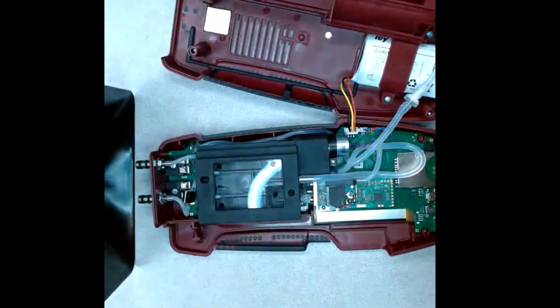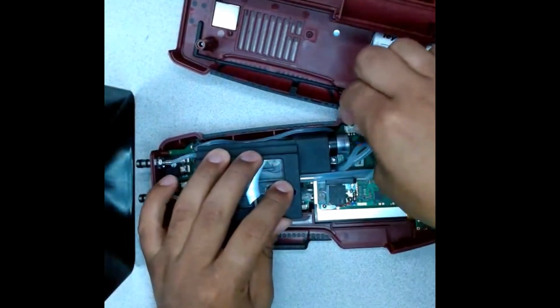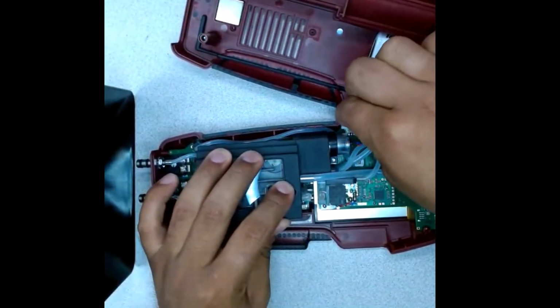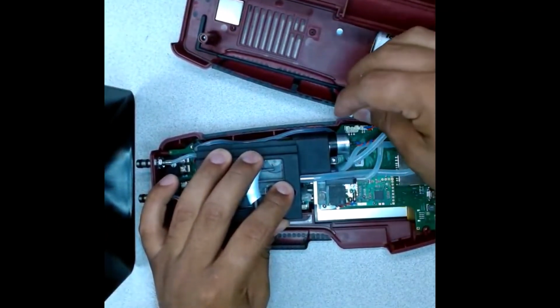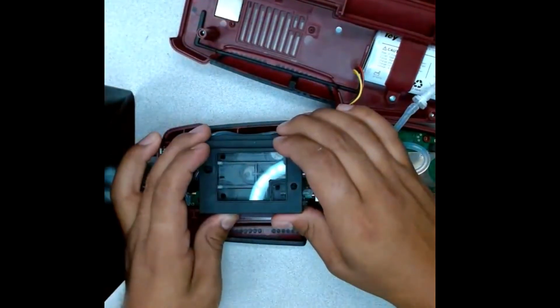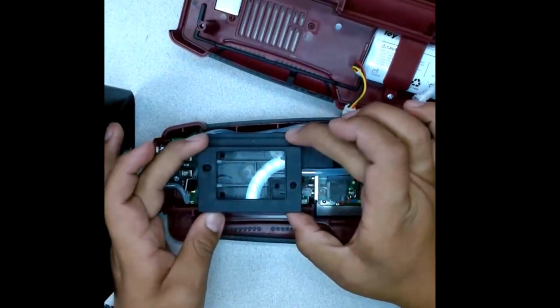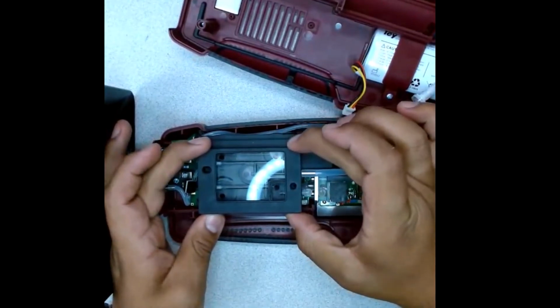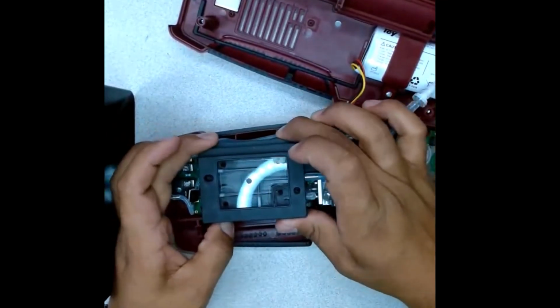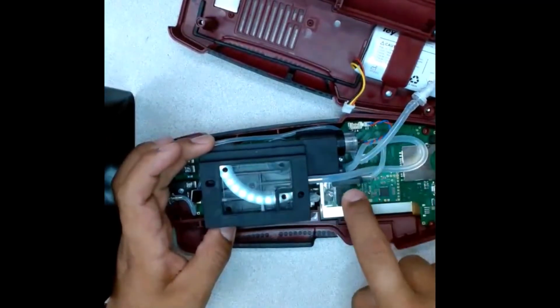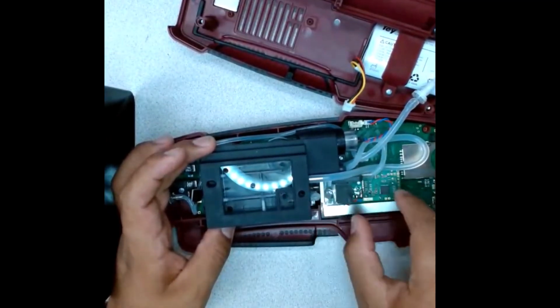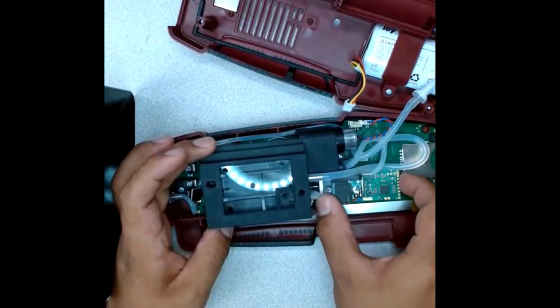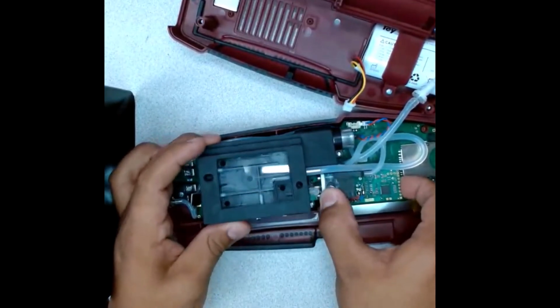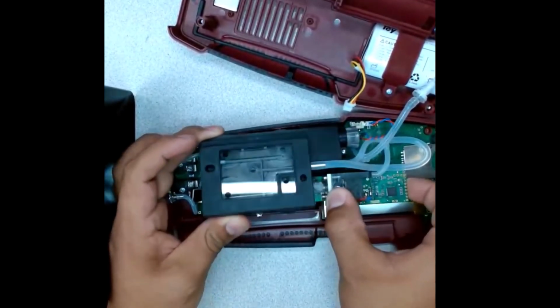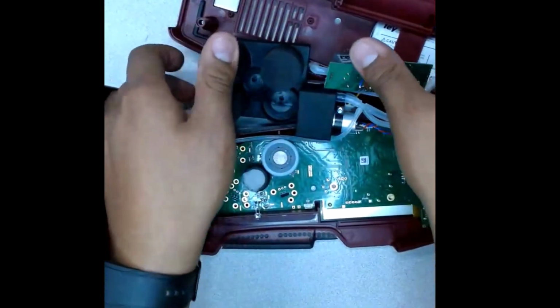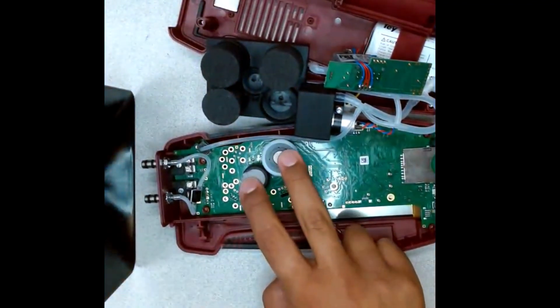And then to replace the sensor, we would recommend to disconnect the battery. It's just a connection right here. So it just plugs in. And then you pull this sensor chamber right here, just a silicone and plastic piece, you pull this straight up, and be careful, this is the infrared right here. This wiggles around. So we can pull that up with it. We want to pull that straight up and then open that as well. And then these are the sensors.